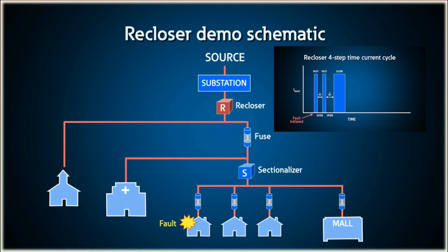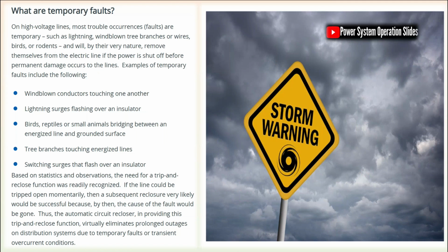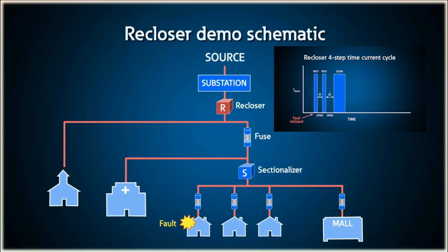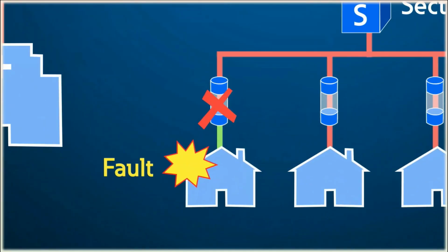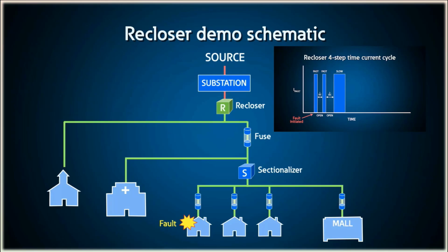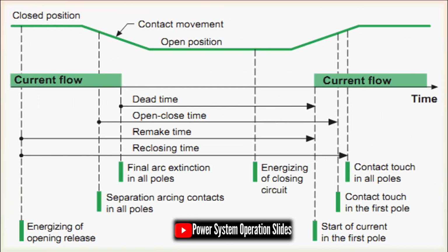Auto reclosers sense and interrupt fault currents and automatically restore service after a momentary outage. Since most line faults, 80 to 90%, are transient, the auto recloser can quickly restore power, preventing prolonged outages. 2. Reduced outage losses. By minimizing outage duration, auto reclosers significantly reduce economic losses for both utilities and consumers. For single-fed radial lines, this is particularly valuable as it prevents extended periods without power.